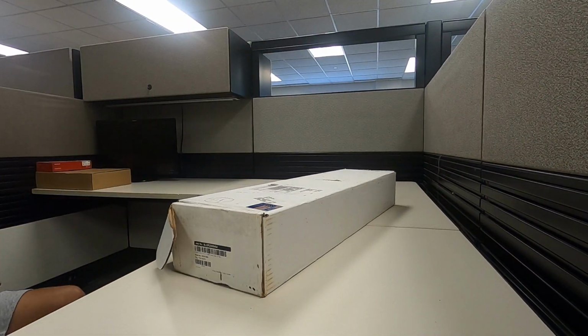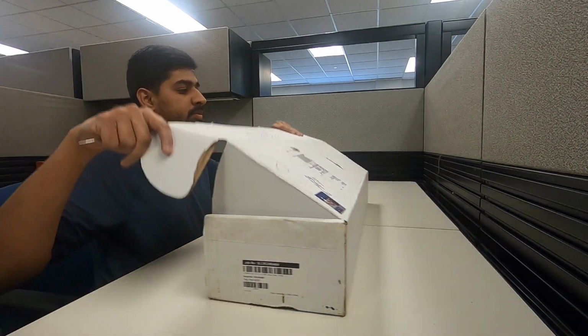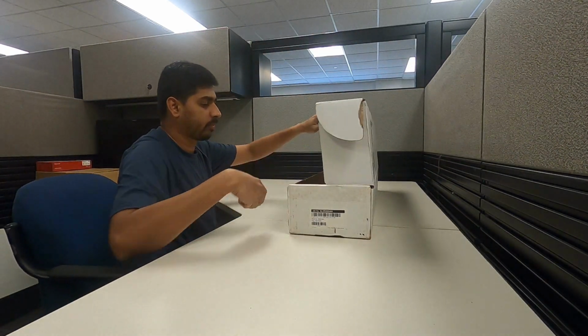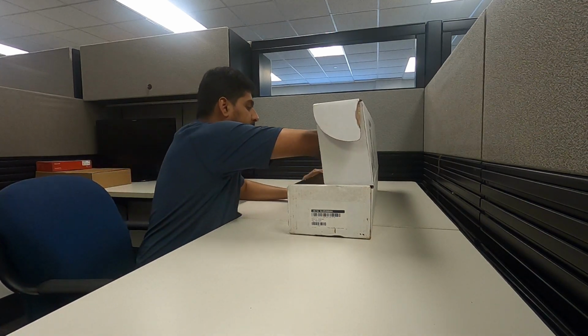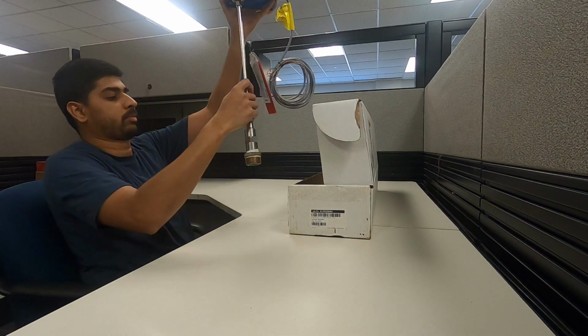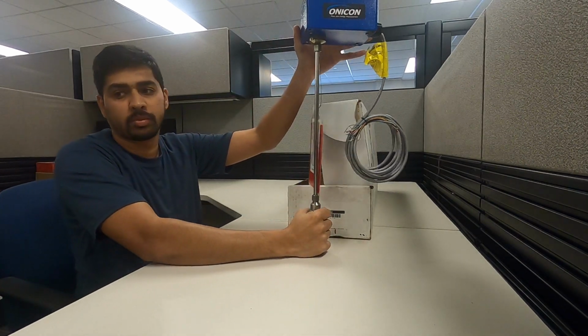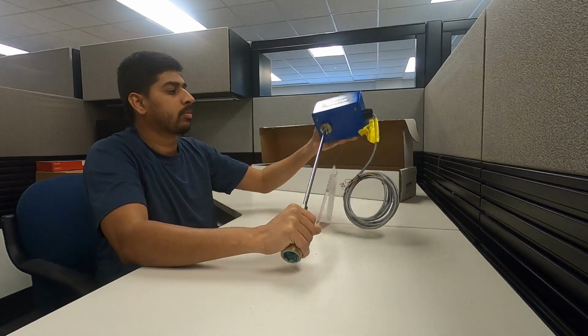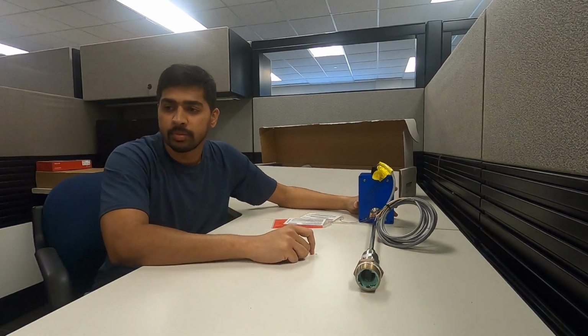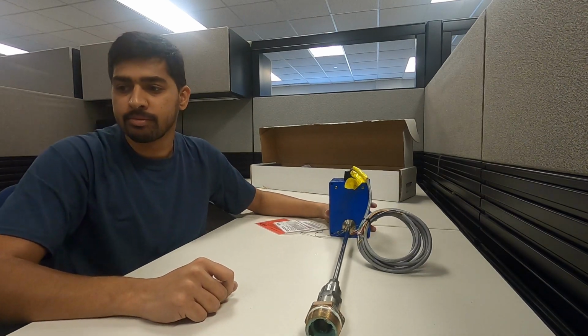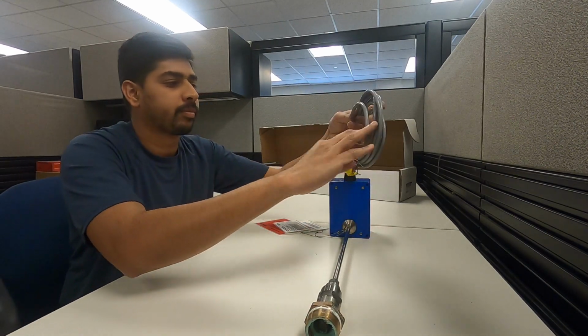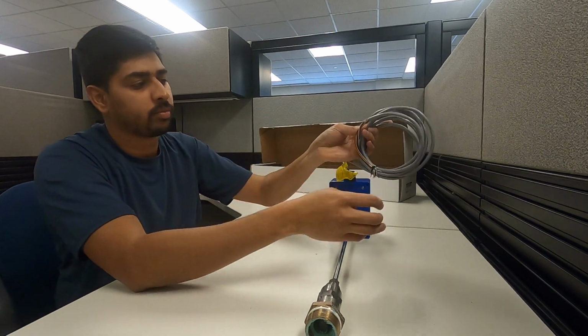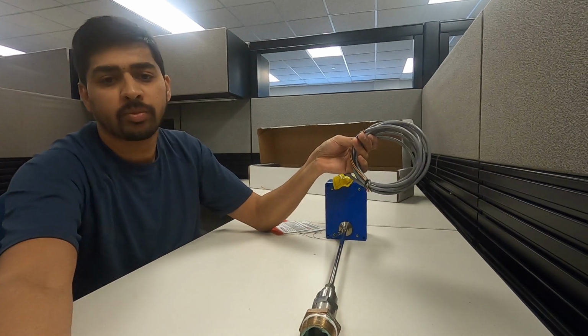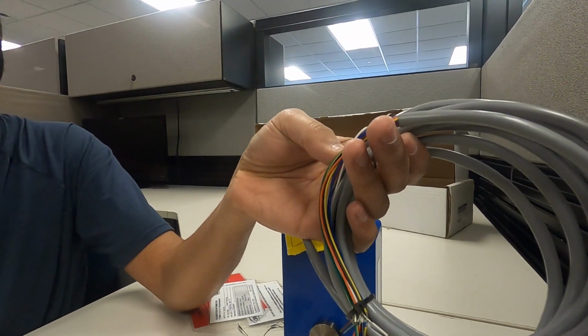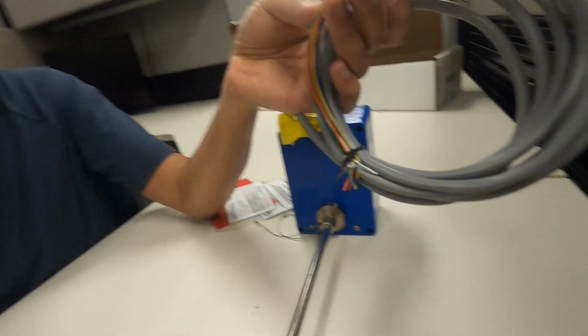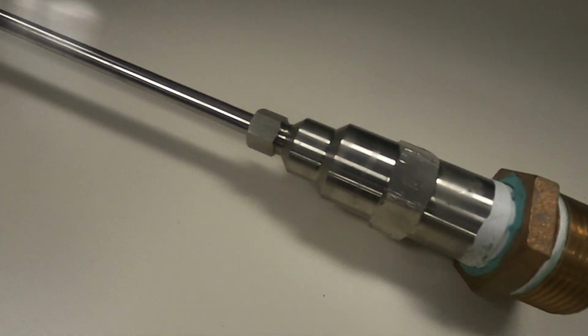Now, the only selection process for these is, say, when you have a mechanical drawing and the specification with you, you will have to be very careful and coordinate with the field guys to see what type of piping they are doing at the site. If the piping they are doing is an Aquatherm pipe, you cannot use the turbine or the electromagnetic flow meter because the Aquatherm pipe cannot have a drill down the pipe and have these things inserted.